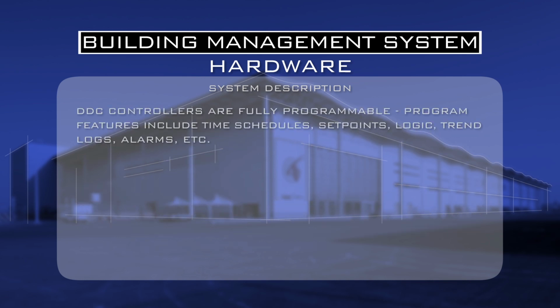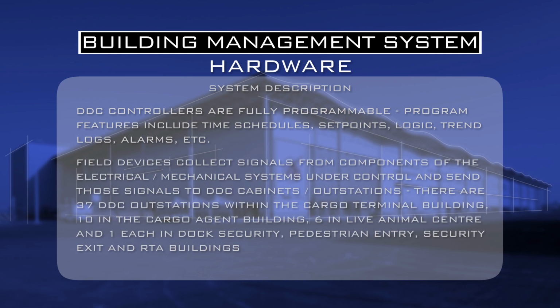DDC controllers are fully programmable. Program features include time schedules, set points, logic, trend logs, alarms, etc. Field devices collect signals from components of the electrical and mechanical systems under control and send those signals to DDC cabinets and outstations. There are 37 DDC outstations within the cargo terminal building, 10 in the cargo agent building, 6 in the live animal centre, and 1 each in dock security, pedestrian entry, security exit, and RTA buildings.